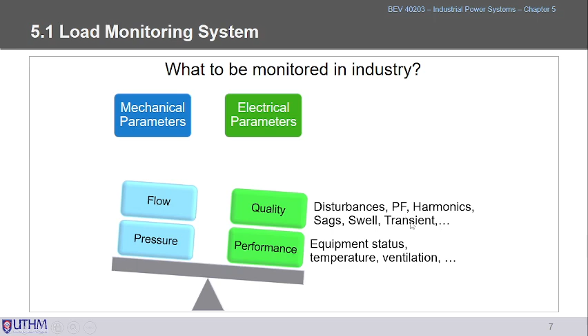Another electrical parameter to monitor is power quality. We have many power quality issues nowadays due to advancements in power electronics devices - a lot of harmonics, voltage sags especially during contingency conditions like faults, and transient effects, for example when switching on and off power factor correctors like capacitor banks.